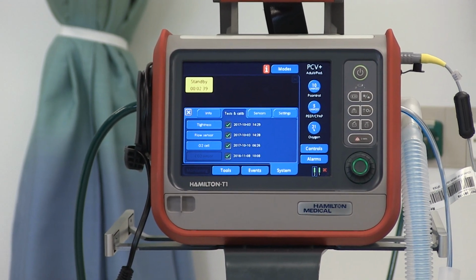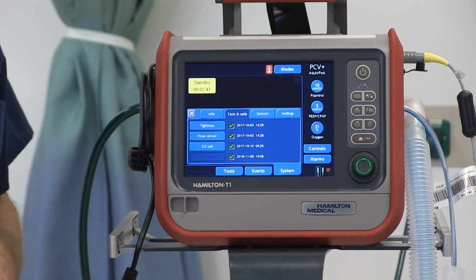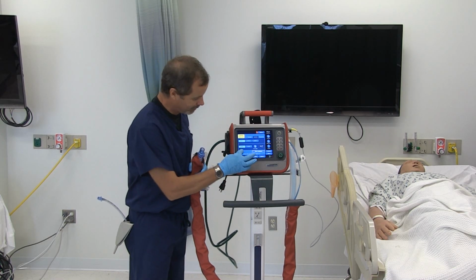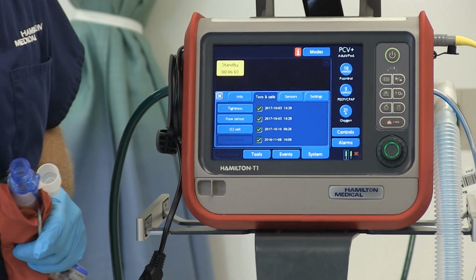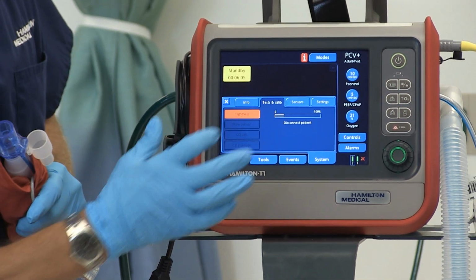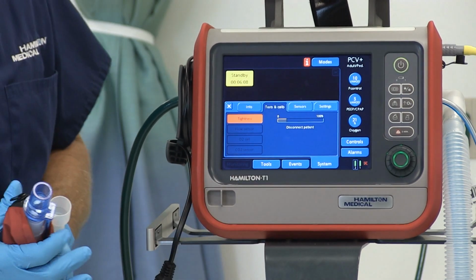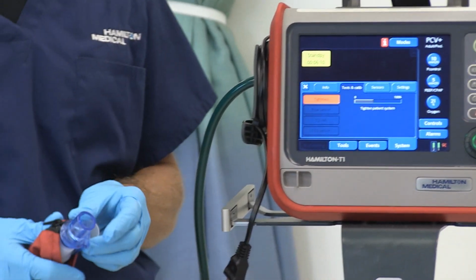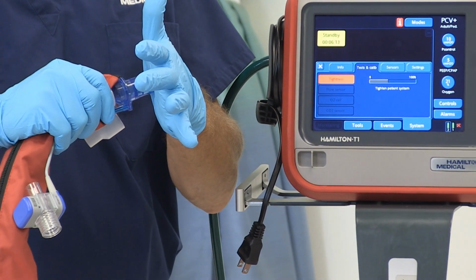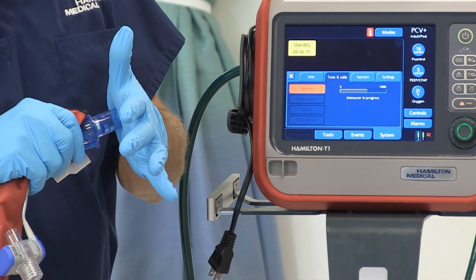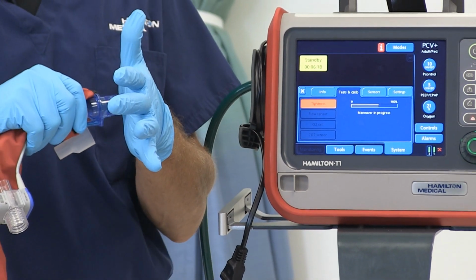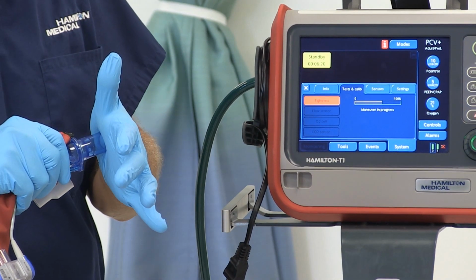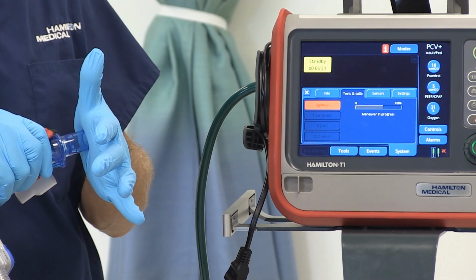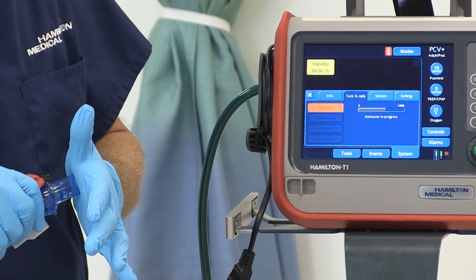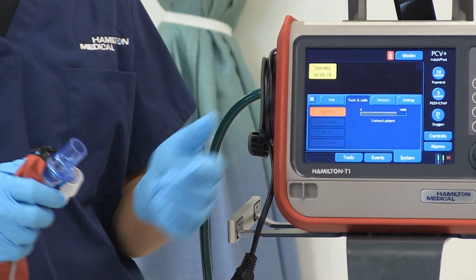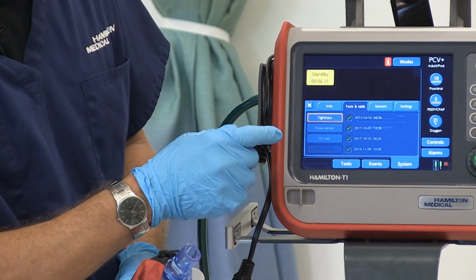The first one is called tightness, and I'm going to put on my gloves. So let's do the pre-op check. You'll see 3 tests. The first is the tightness check. Press that button. On the screen, it's going to give you directions as to what to do next. Now it says tighten patient system, so I'll take my gloved hand and occlude the circuit. Now it's going to pressurize up to 60 centimeters of water pressure and look for leaks. And I'm going to watch the screen to tell me what to do next. Connect patient just means that test is finished. So now we can move on to the next test.